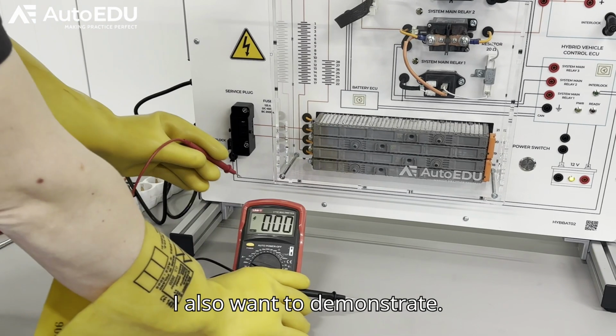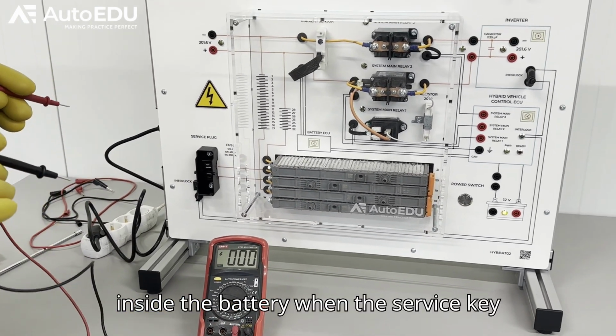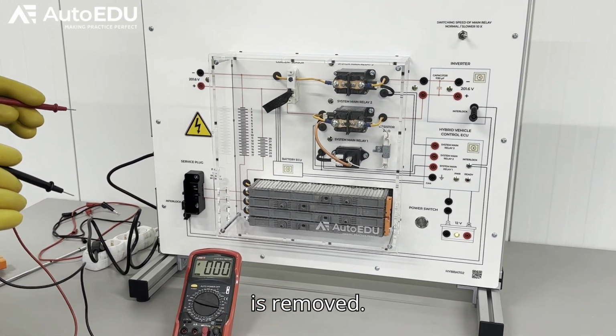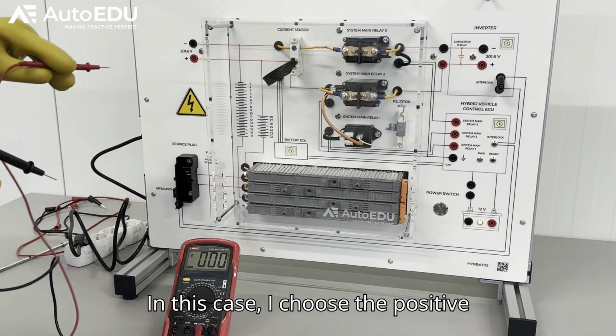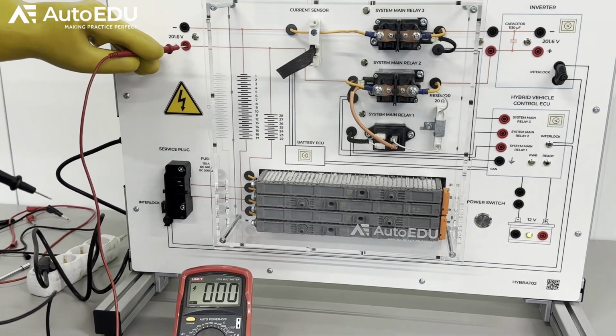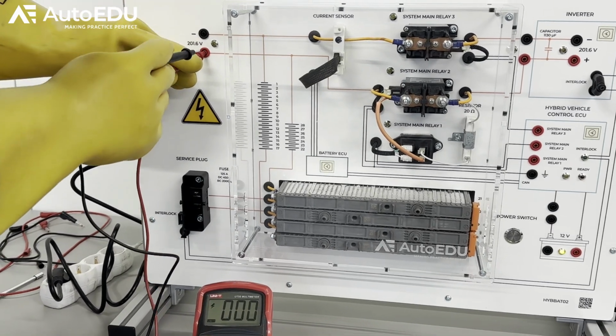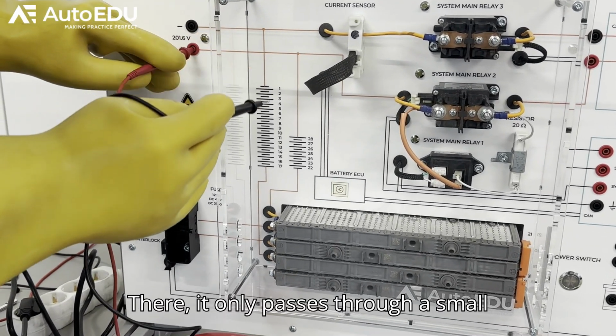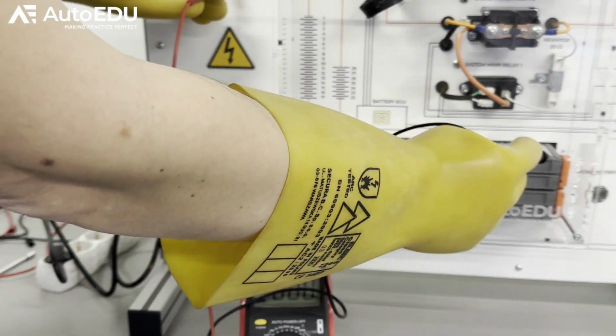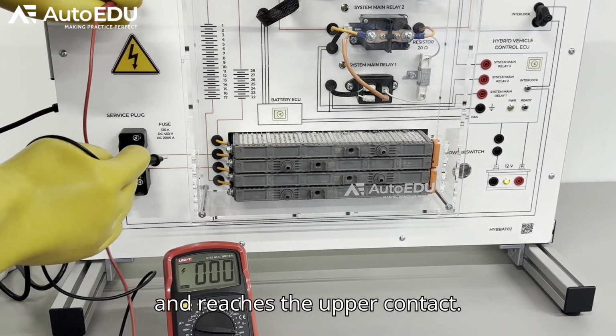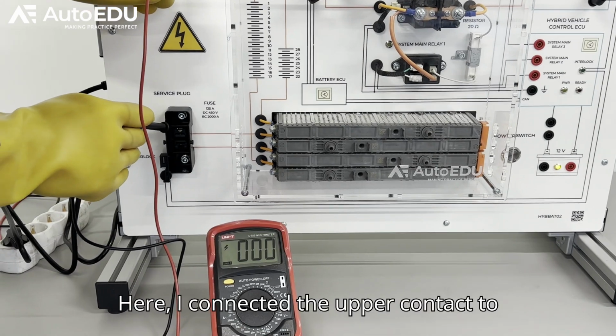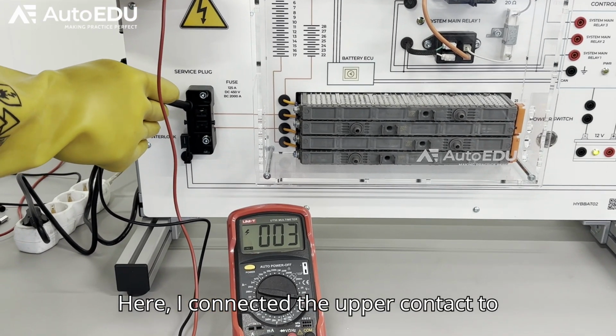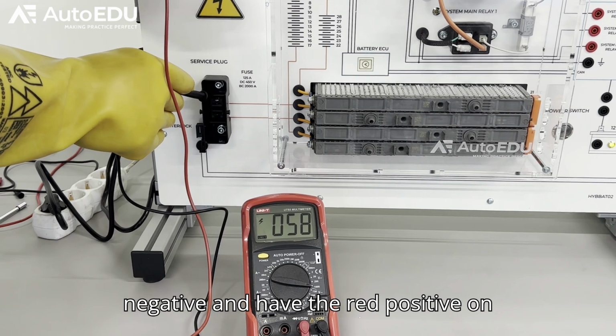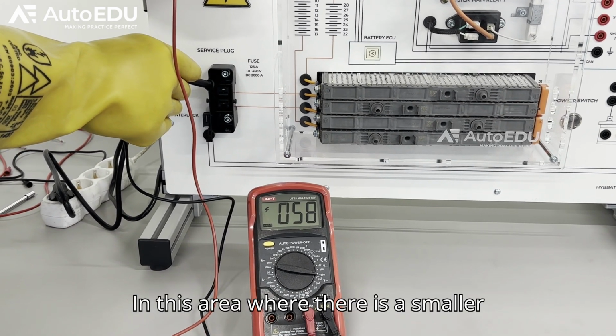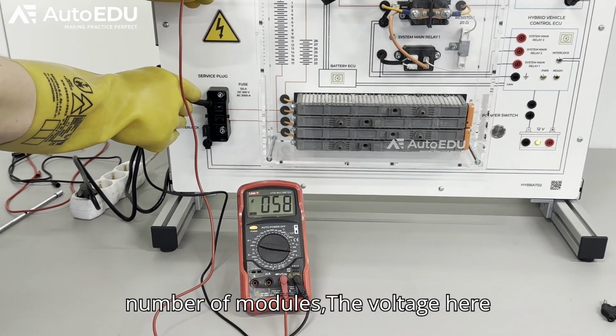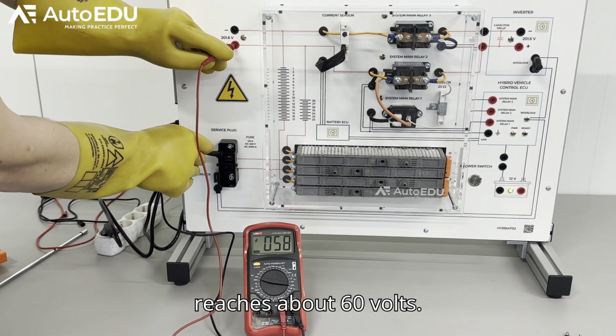I also want to demonstrate how to measure the voltage remaining inside the battery when the service key is removed. In this case, I choose the positive terminal. I trace where the wire goes. There, it only passes through a small part and reaches the upper contact. Here, I connected the upper contact to negative and have the red positive on top. In this area, where there is a smaller number of modules, the voltage here reaches about 60 volts.